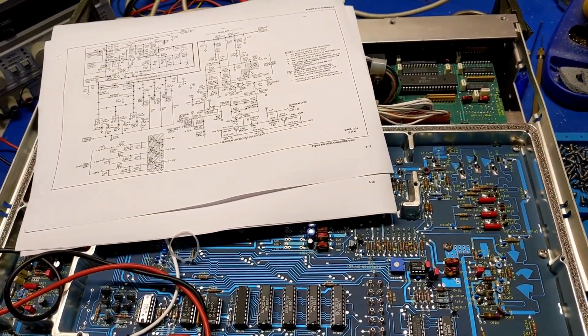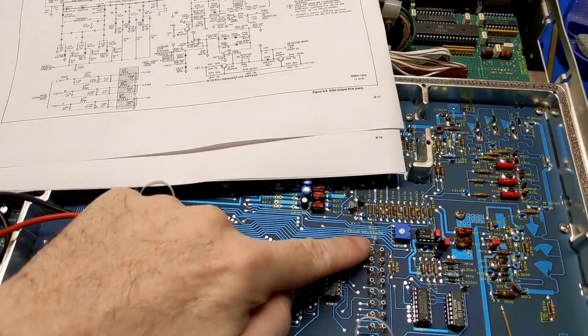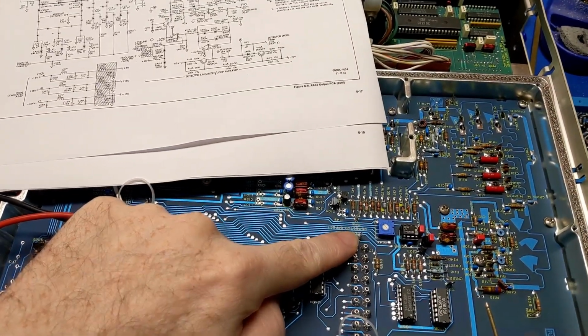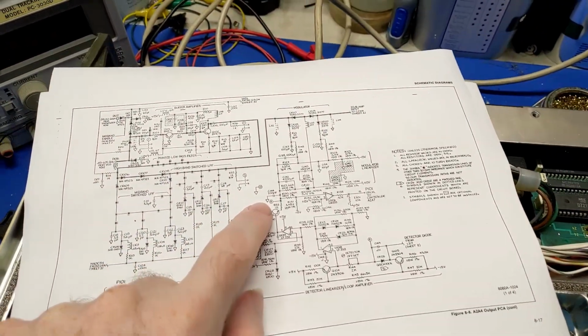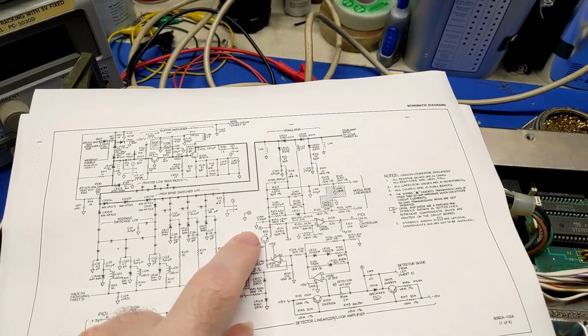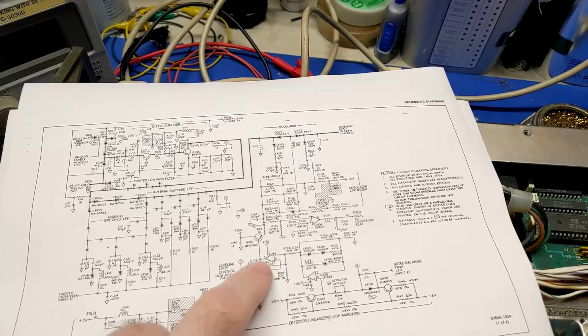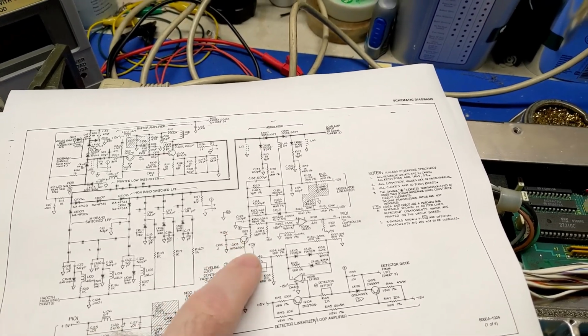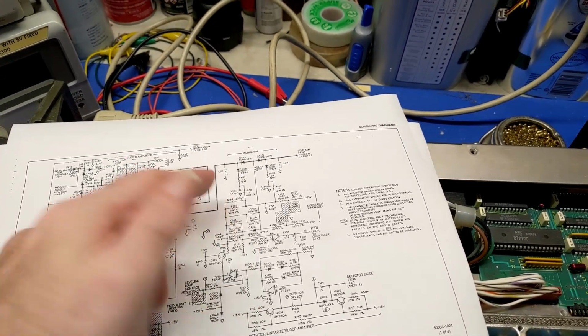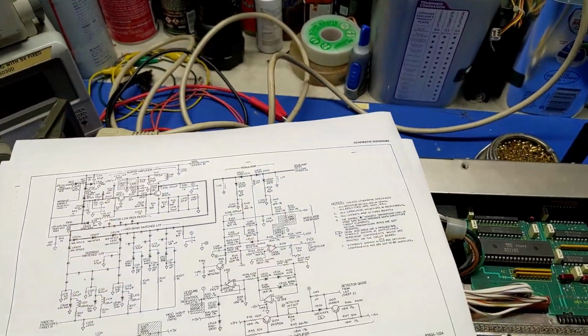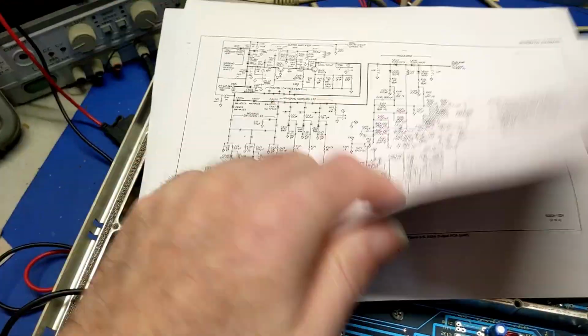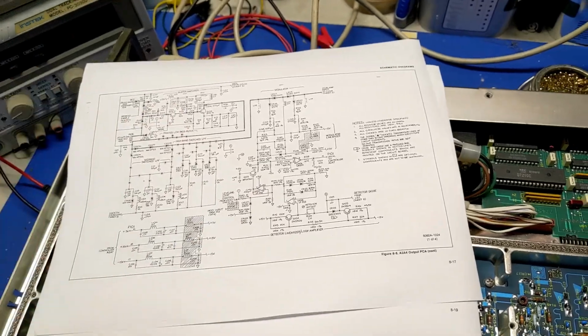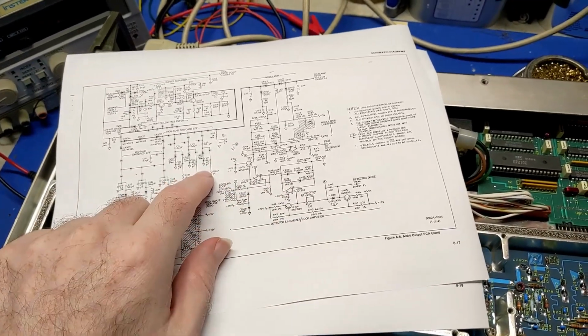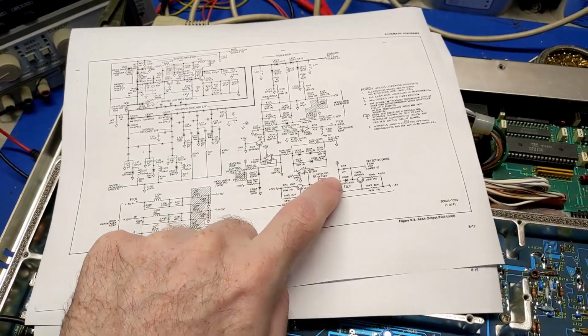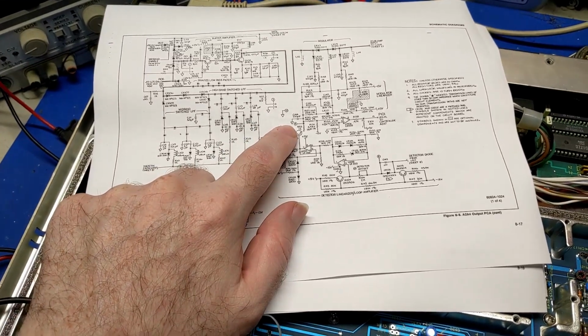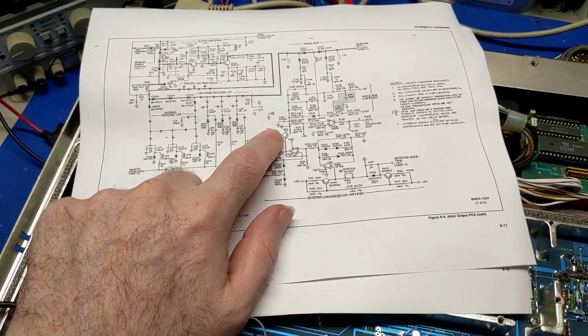I got to make a correction on my previous point here. I was testing this point there, I'm pretty sure, which is here, which is why it's being driven high when I'm in the low band, because this is the error amplifier output. So this was swinging way high because it was trying to push as much RF as it possibly can through the 20 dB amplifier. So regardless, the fault is still the same, whether I'm probing 8 or I'm probing 6. Point is, I'm looking at the error output level, and it's way, way high.